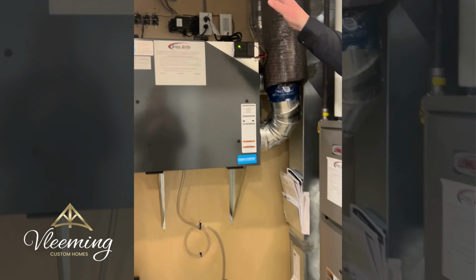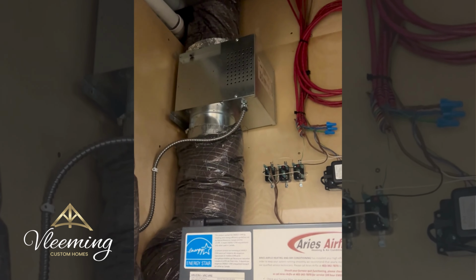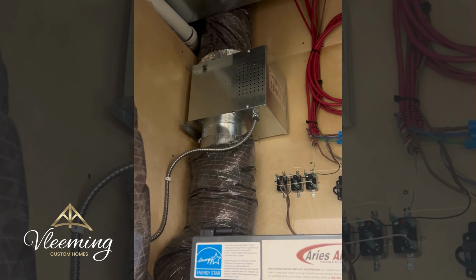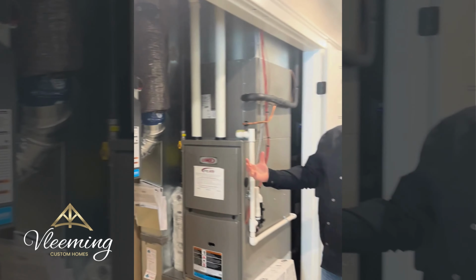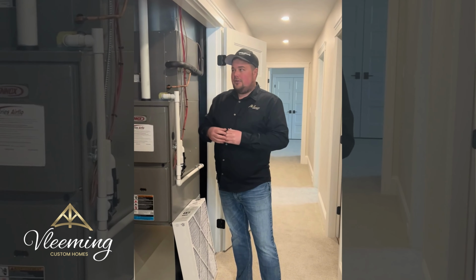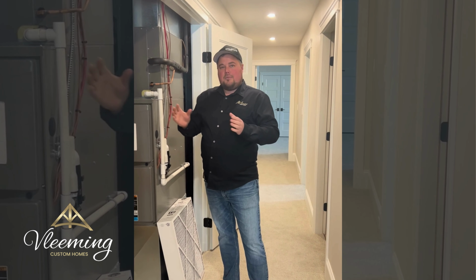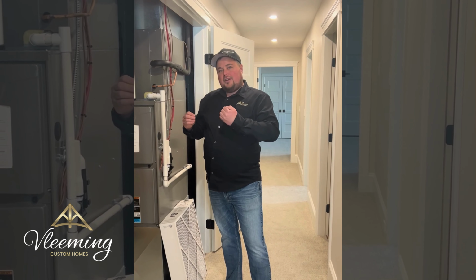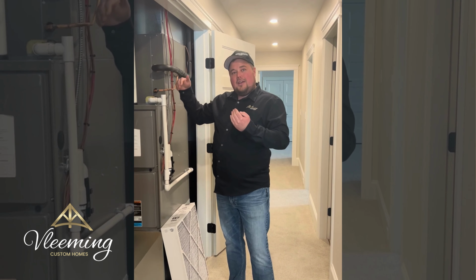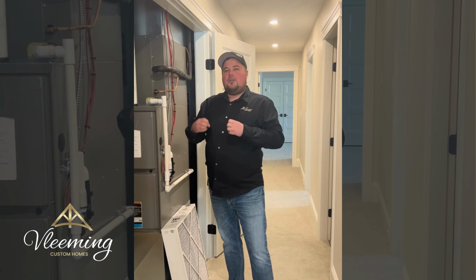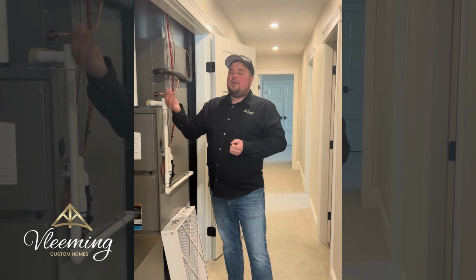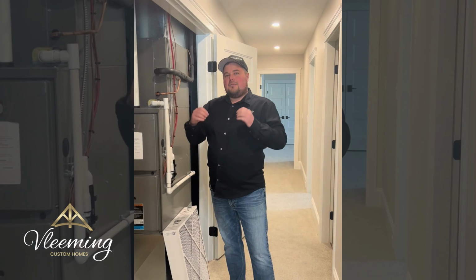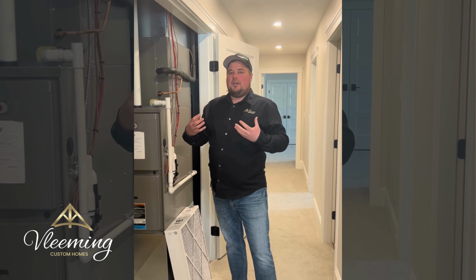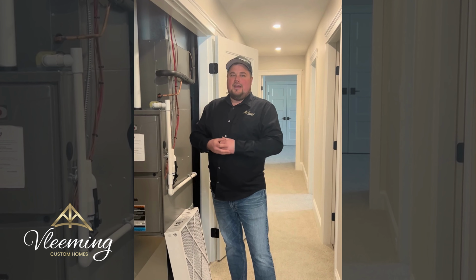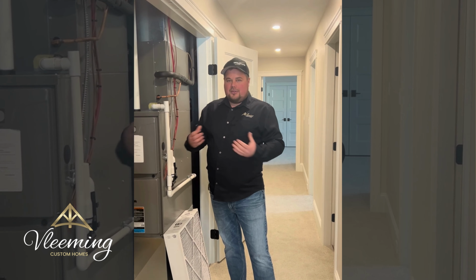Attached to the HRV up in the corner here is a little preheater. The reason we have that is HRVs have a point where their efficiencies aren't as great and where they can start freezing up. And because we're here in Alberta, we get some cold days once in a while. So when you get that minus, call it 40 temperature range, where you could be getting very cold air into that HRV and that nice, moist, warm air is going back out, it could potentially cause a freeze up inside. So by putting that preheater in there, it's set to preheat that really, really cold air only when it's cold, just so you don't have a problem with the HRV. Simple little precaution just to help the scenario again.